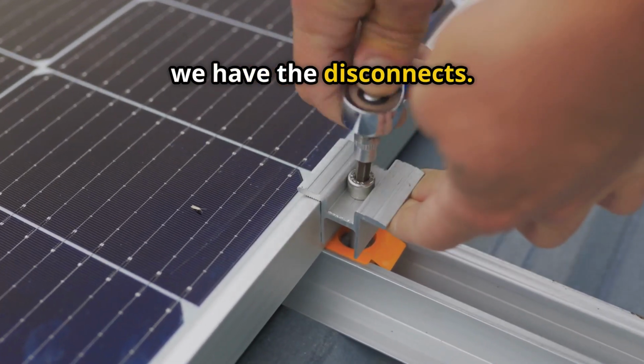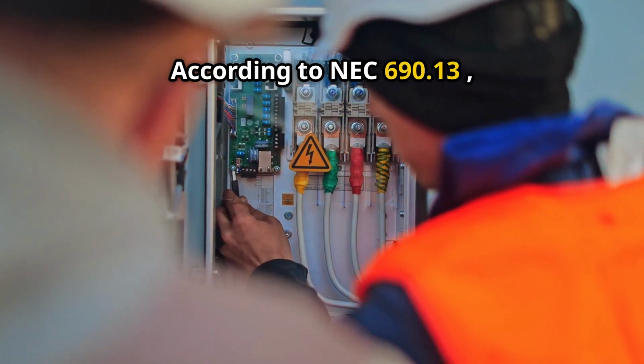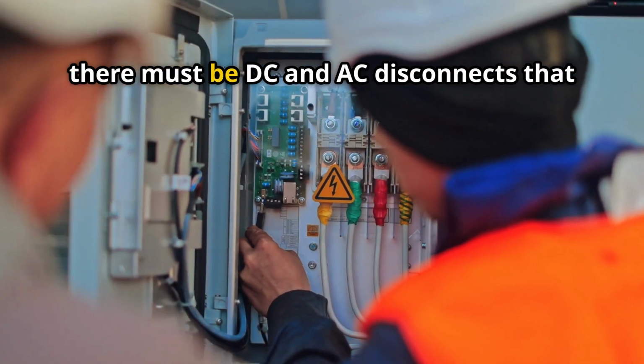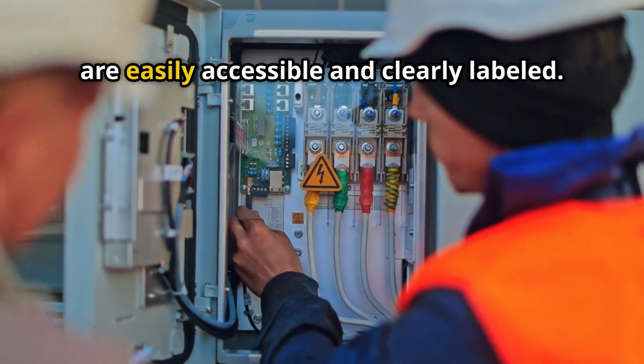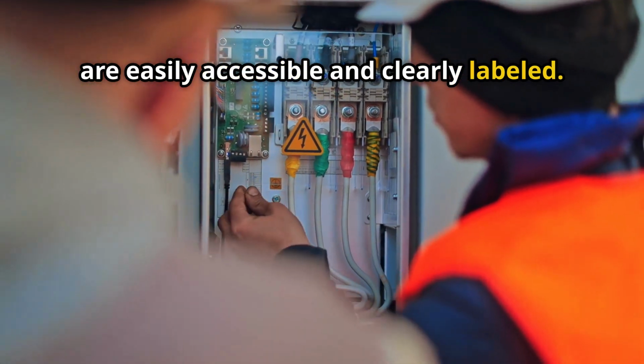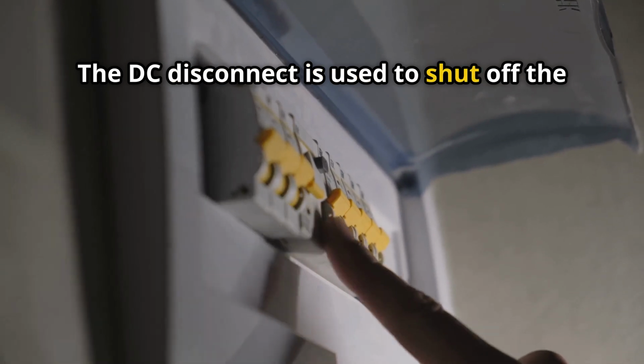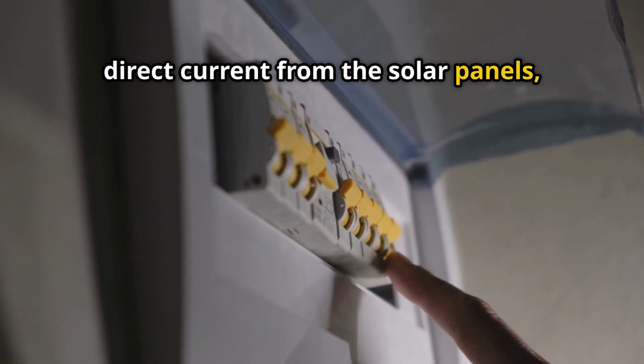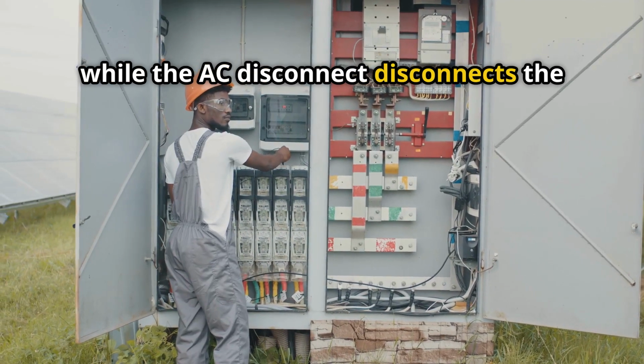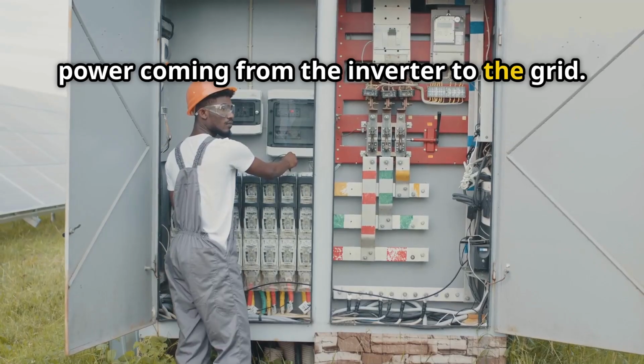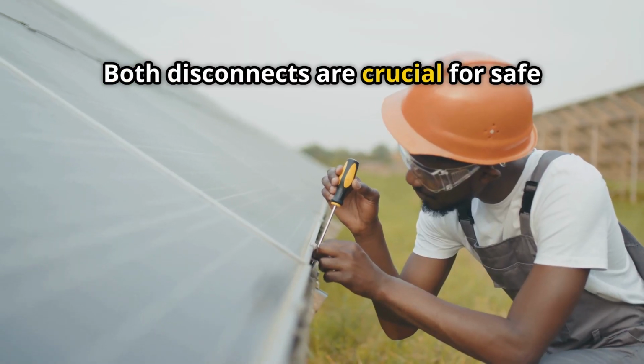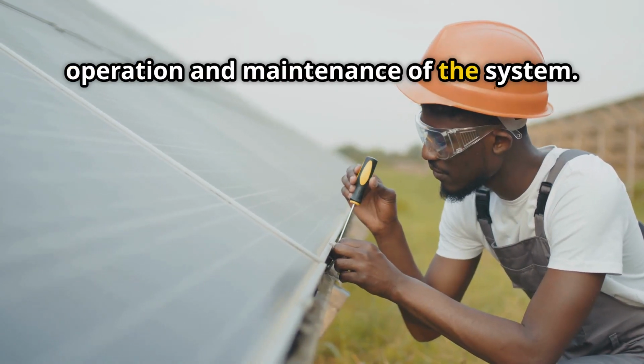Next, we have the disconnects. According to NEC 690.13, there must be DC and AC disconnects that are easily accessible and clearly labeled. The DC disconnect is used to shut off the direct current from the solar panels, while the AC disconnect disconnects the power coming from the inverter to the grid. Both disconnects are crucial for safe operation and maintenance of the system.